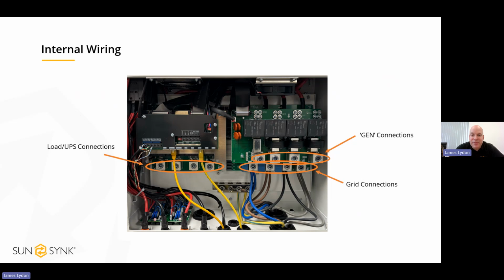So this is showing you the 50 kilowatt. We've used this image just because obviously it's bigger, it's a little bit clearer. You can see you've got your three different inputs and outputs. So starting off on the left, you've got your UPS connection. So that's your off-grid load. Then top right, you've got your generator connections. And then at the bottom, you've got your grid connection. And then just below all that, you can see there's a common earth at the bottom.